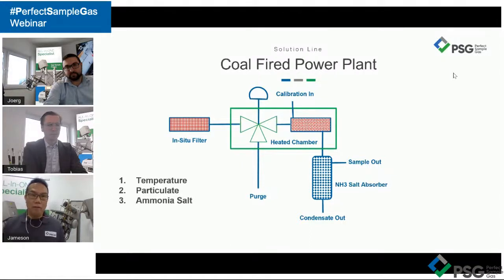All right, so those are very, very clean. It's easy to overcome. But for a coal-fired power plant, with a high amount of SO3, high amount of particles, high amount of water, and all these things that come into effect, you don't want to buy the wrong sample probe, and you don't want to engage so many of your labor hours to attend to the probe. So when you look at the probe, it is important that there are two filters.